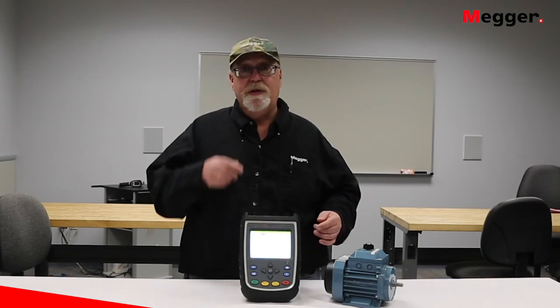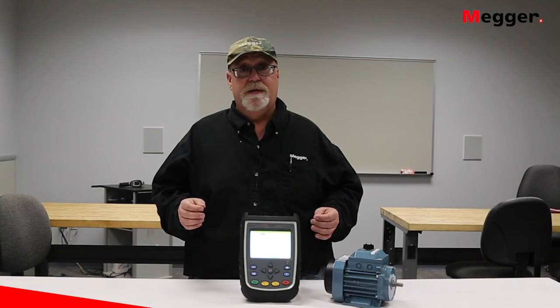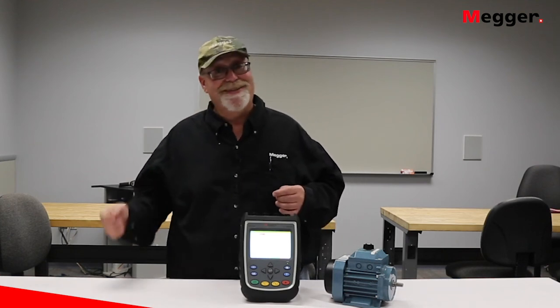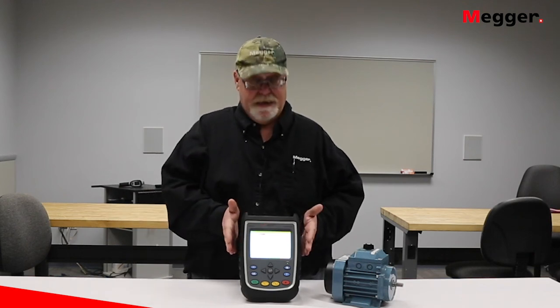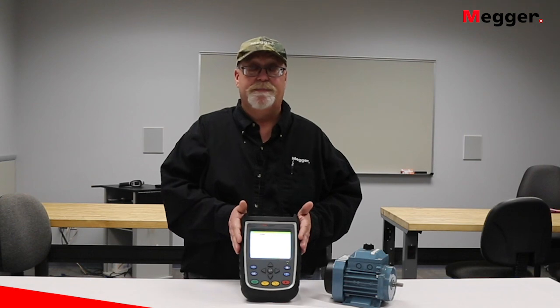The MPQ has a recording scope ability, so you can leave the unit connected, and not only will it record inrush current, but it will periodically capture timed waveforms up to 200 cycles each. So you can leave the unit in place for months on end, and it can help locate those intermittent problems.